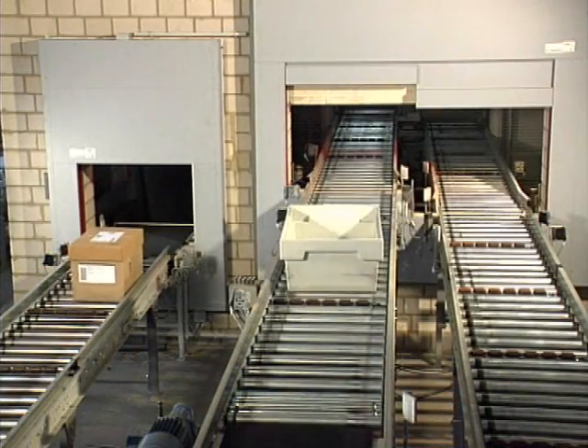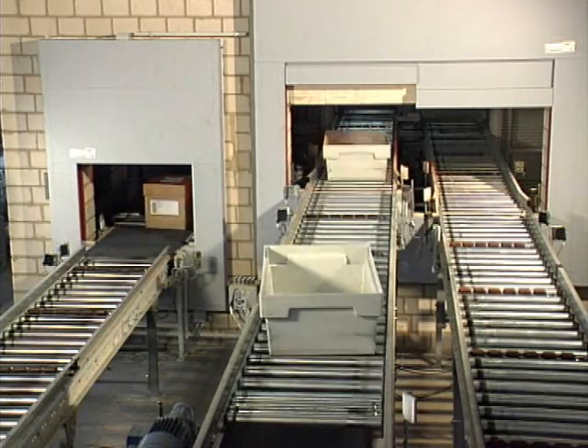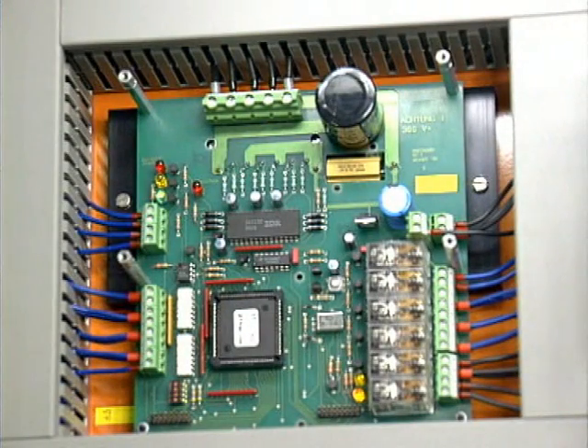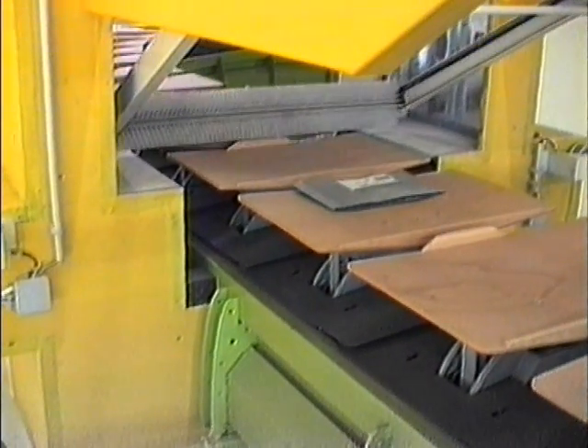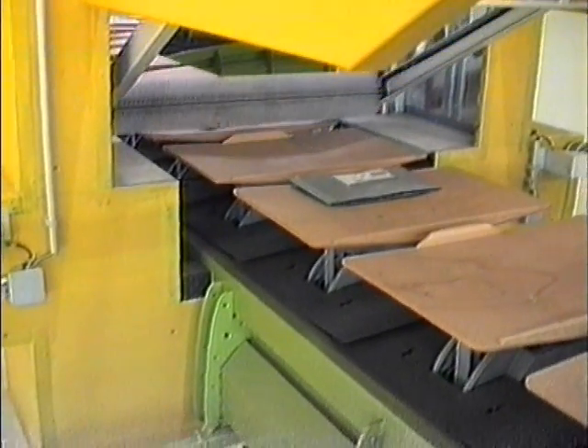To provide efficient fire protection, no changes were required, even for this roller conveyor. In case of fire, a gap in the lower part of the door will safely enclose the bridging roller of the conveyor system. In case of fire, intelligent control elements or clearing systems with high potential, respectively mechanical spring-type energy, ensure the clearing of the closing area. For example, this special type for tilting conveyors.